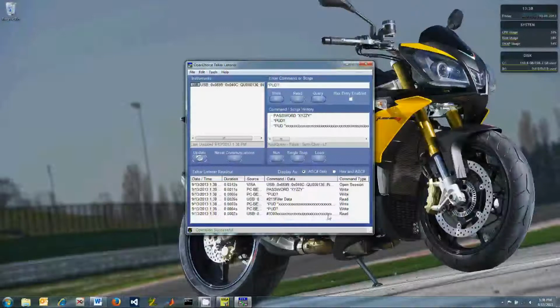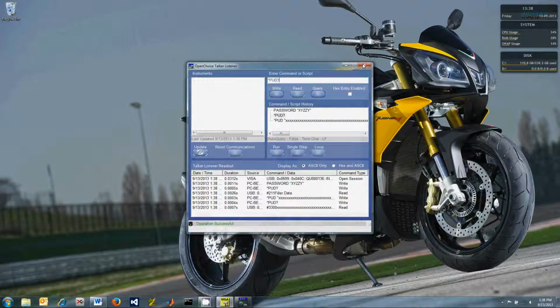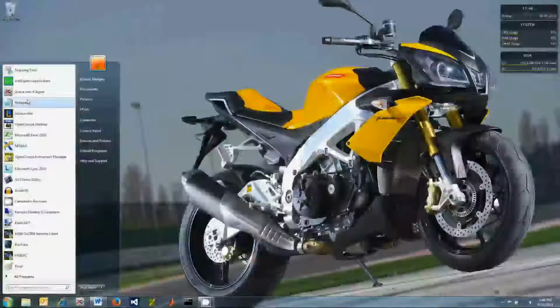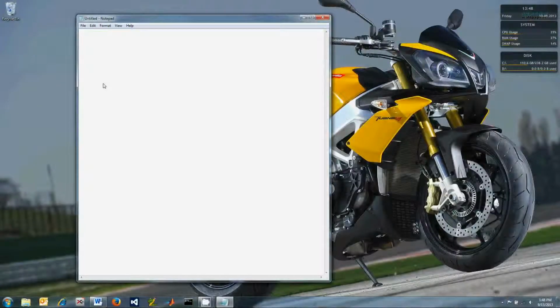If you can't connect your scope to a computer, you can write these commands into a setup file and run it on your scope to erase the protected user data. Open a basic text editing application such as Notepad and type the following into it. Colon password, and then in quotations, XYZZY.